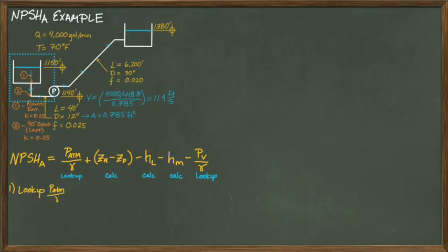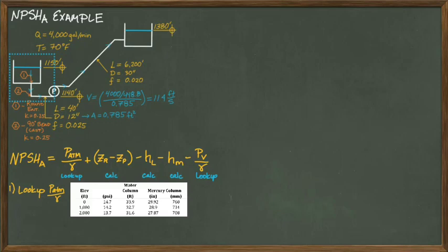There are many resources that provide information about the atmospheric pressure at different elevations. This table shown in this video comes from Pumping Station Design 3rd Edition. The appropriate atmospheric pressure for our example is measured at the suction flange of the pump. In this case, we want to know the atmospheric pressure at 1,140 feet above sea level. This means we need to interpolate between the values of 14.2 psi and 13.7 psi, because our elevation is between 1,000 and 2,000 feet. We start with 14.2 minus 0.14 because we are 140 feet, or 14% of the distance between 1,000 and 2,000 feet.